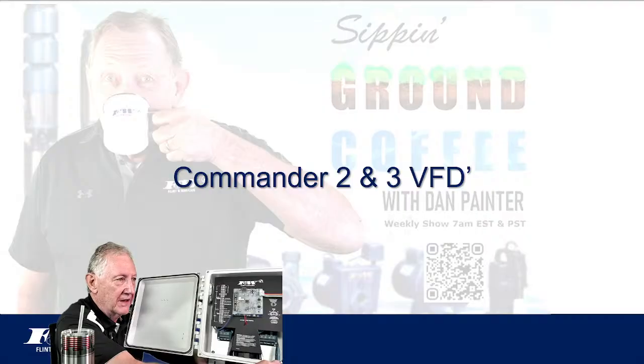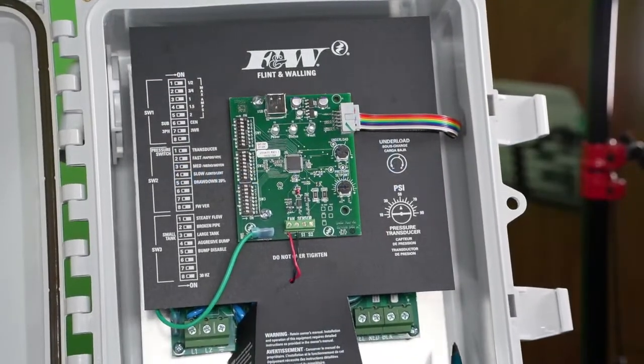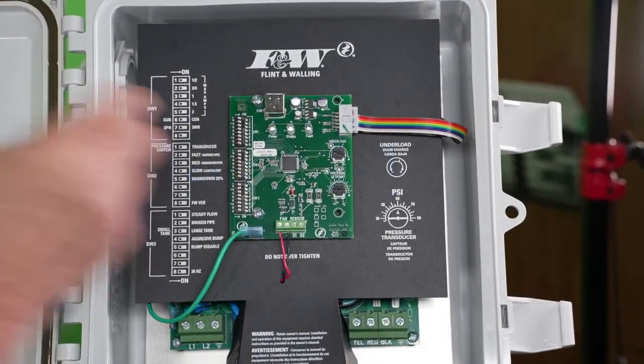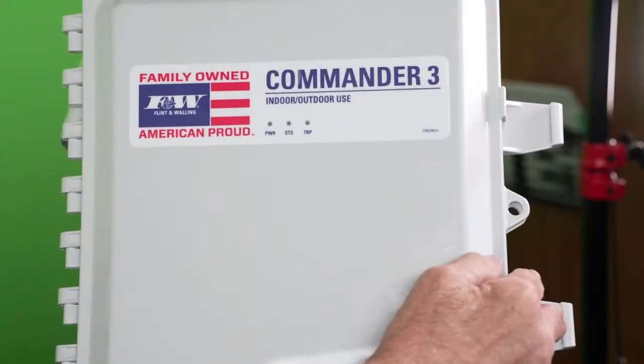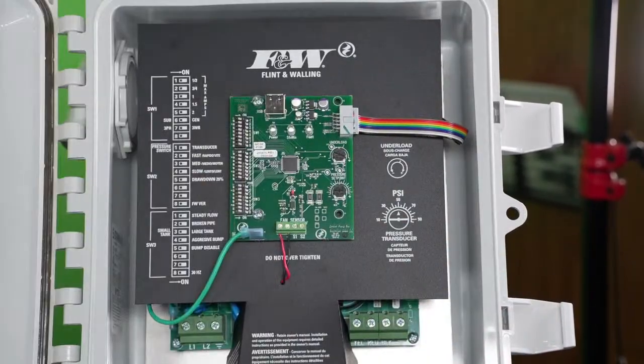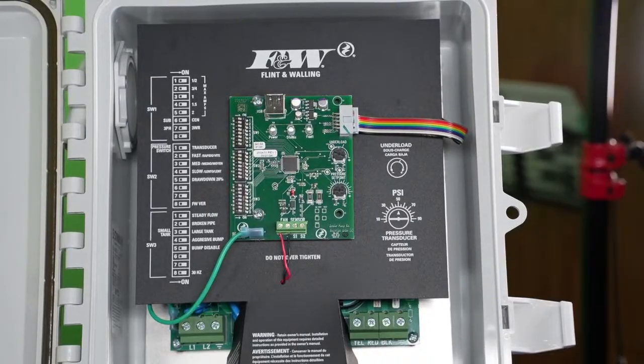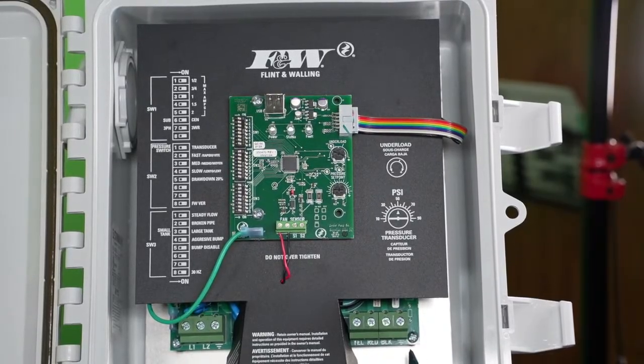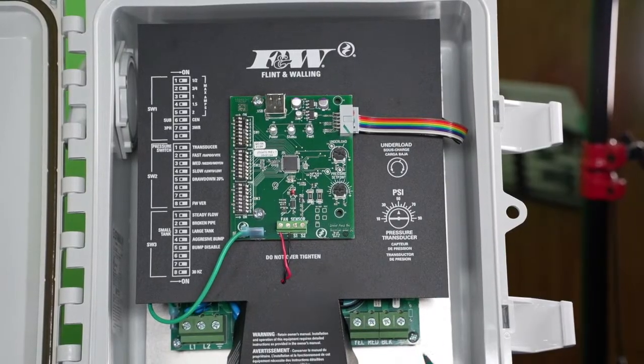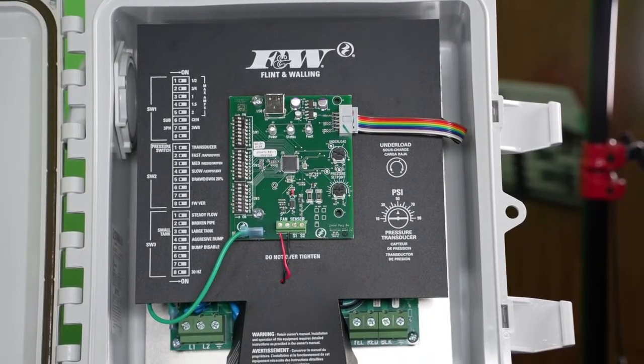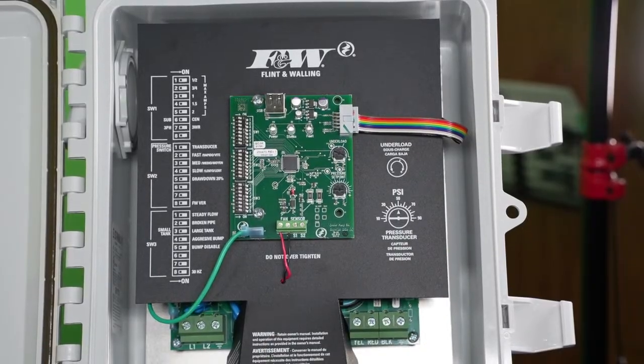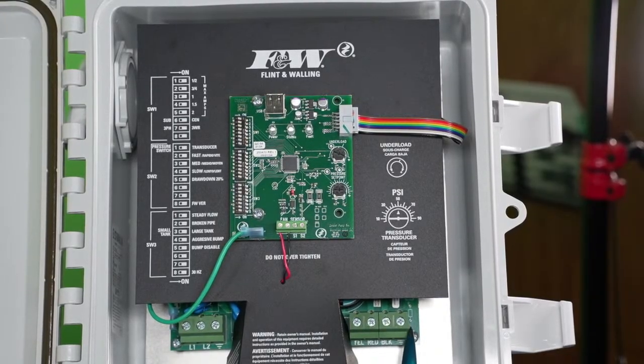Just on the other side over here is another terminal block, and this will be your power out to your pump. This is a Commander 3 drive, and so down here we're going to have 4 terminals. You're going to have your black, your yellow, your red, and your green ground over here. On the Commander 2 models, that terminal block will only have 3 terminals on it because all you have on the Commander 2 is 2 blacks and a green wire.